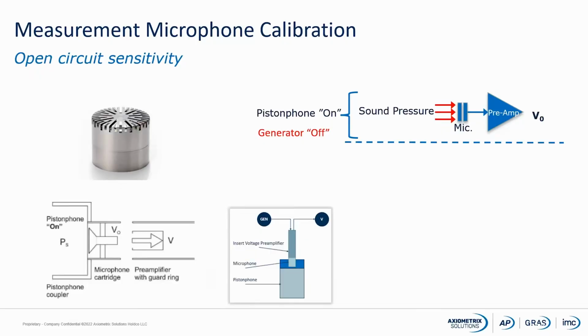How to measure the open circuit sensitivity. It is done in two steps. First of all, we will mount only the microphone capsule on a preamplifier, and this is a special preamplifier. It is called an insert voltage preamplifier. When we have mounted it on this preamplifier, we will mount the microphone inside our piston phone, because with the piston phone we know exactly the pressure we have. So we will start measuring the output of the microphone and of course the preamplifier, and it is equal to VO.